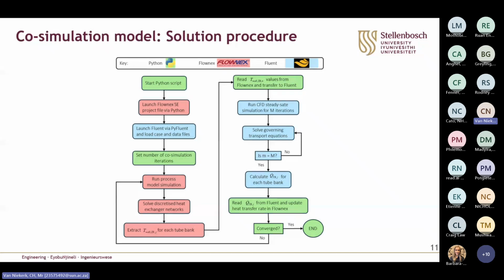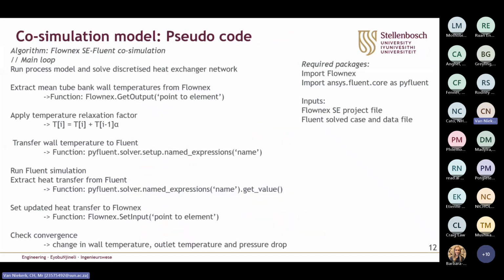in the CFD model. The CFD model is then instructed to complete a few iterations, and after that, we can calculate the total heat transfer entering the air, which is then passed via Python into Flownex again, and then updates the process and updates these wall temperatures until we've established convergence between the two models. And this was done by just monitoring the governing equation residuals in Fluent, as well as overall performance parameters such as the total heat transfer and air mass flow rate.